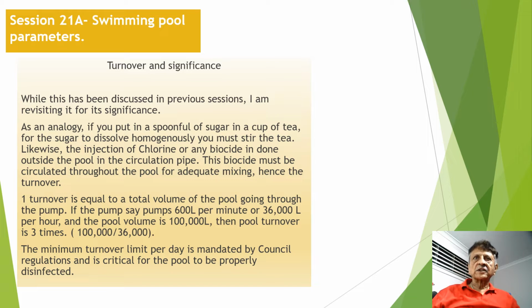The definition of turnover: one turnover is equal to the total volume of the pool going through the pump. If the pump, say, pumps 600 liters per minute or 36,000 liters per hour, and the pool volume is 100,000 liters, then the pool turnover is 3 times. That is about 100,000 divided by 36. The minimum turnover limit is mandated by regulations, and it is critical for the pool to be properly disinfected.